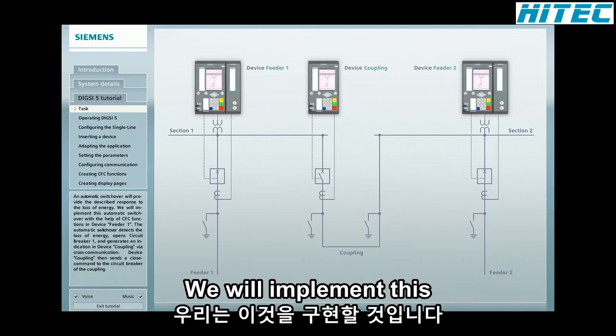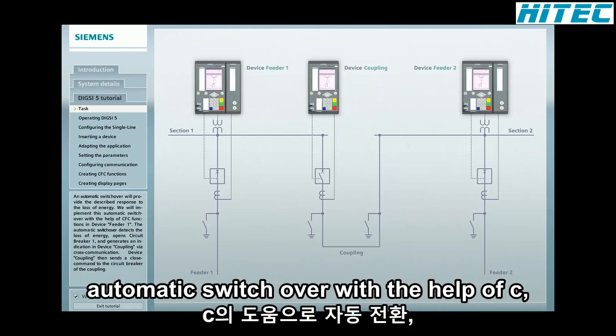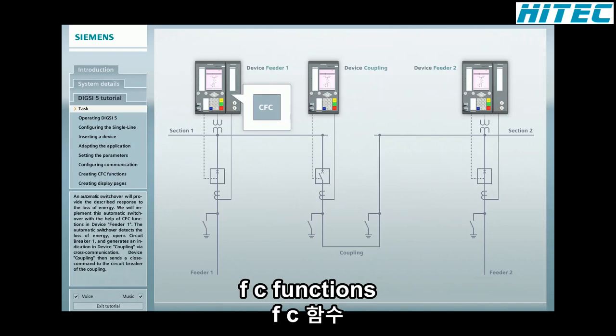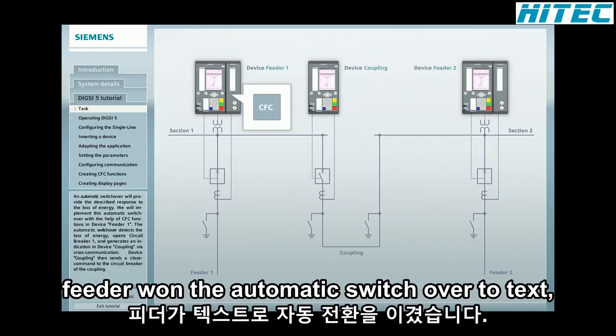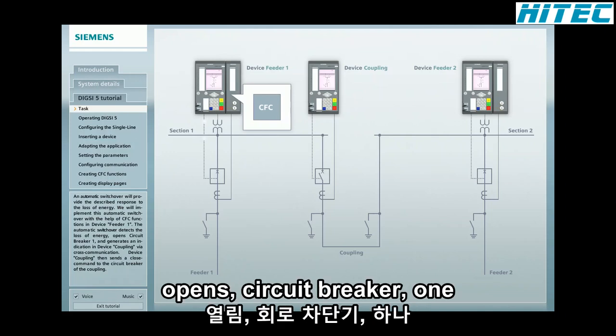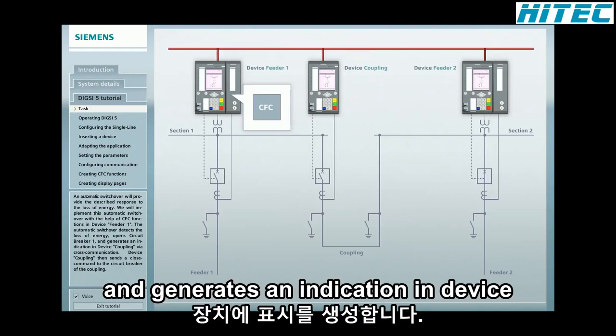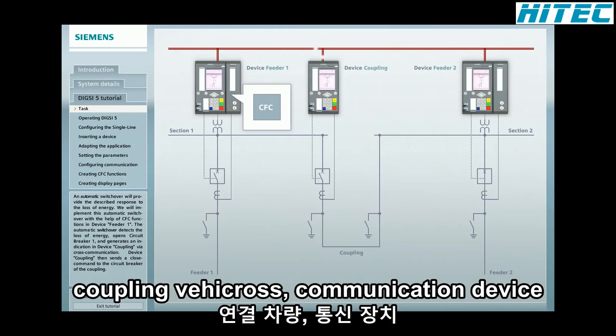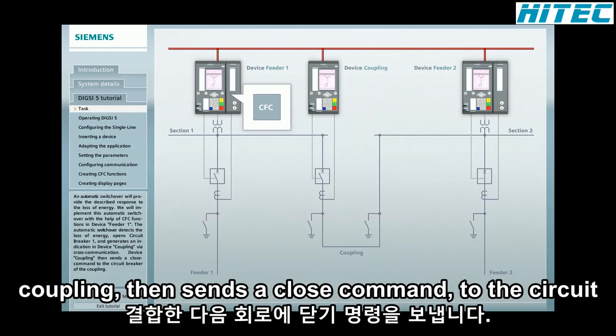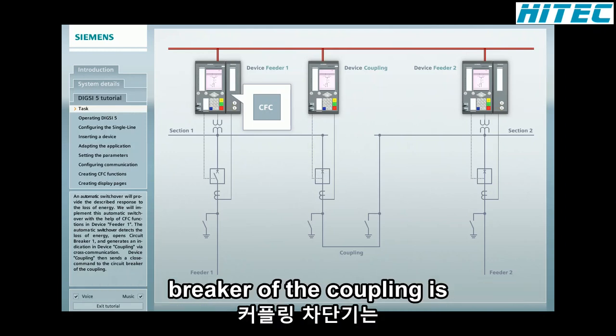An automatic switchover will provide the described response to the loss of energy. We will implement this automatic switchover with the help of CFC functions in device feeder 1. The automatic switchover detects the loss of energy, opens circuit breaker 1, and generates an indication in device coupling via cross communication. Device coupling then sends a close command to the circuit breaker of the coupling.